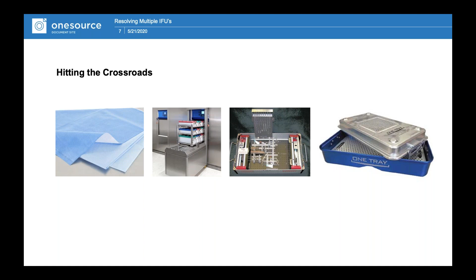If we jump over to the next slide, this is where I was thinking after looking at this scenario: we have an instrument going inside of a rigid container, which is then going inside of an autoclave. So there's an IFU for the device and an IFU for the rigid container. Rigid packaging systems have their own 510K. A medical device does, and so does a sterilizer.